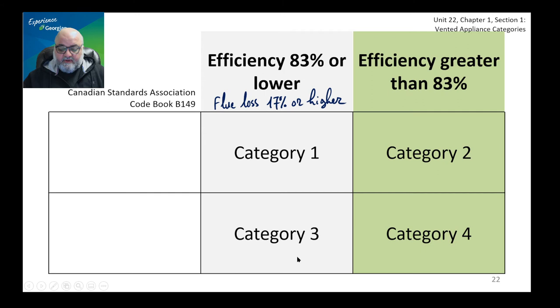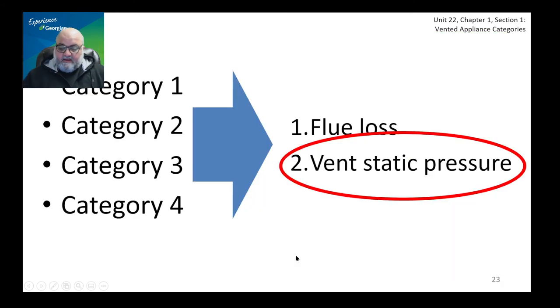So efficiency of 83% or lower is category 1 or 3, because that equals flue loss of 17% or higher. If the appliance has an efficiency greater than 83%, it means flue loss is less than 17% — that would be category 2 or 4. The question then becomes: how do we distinguish between category 1 and category 3, or between category 2 and 4? That brings us to vent static pressure.